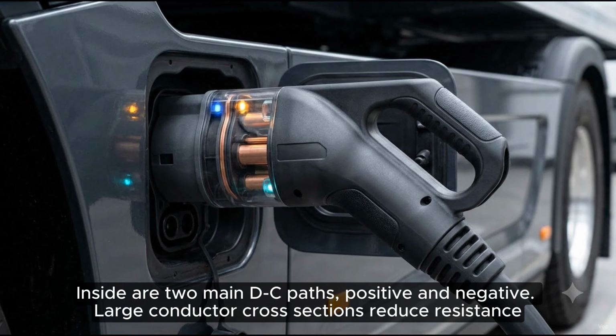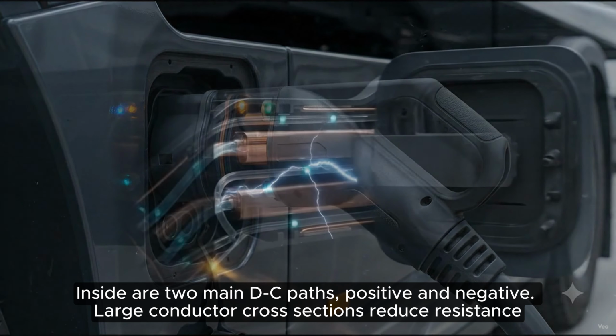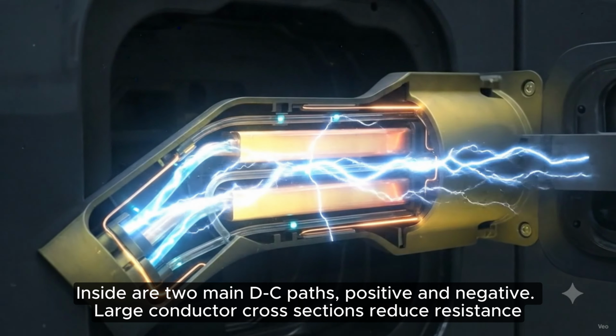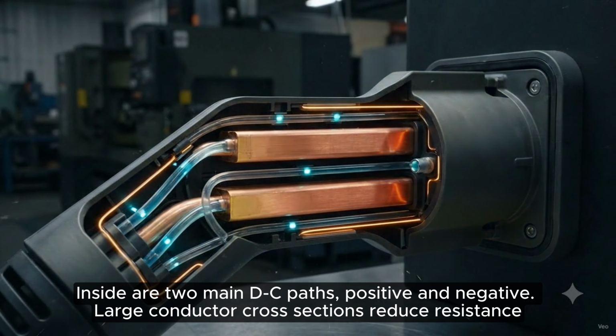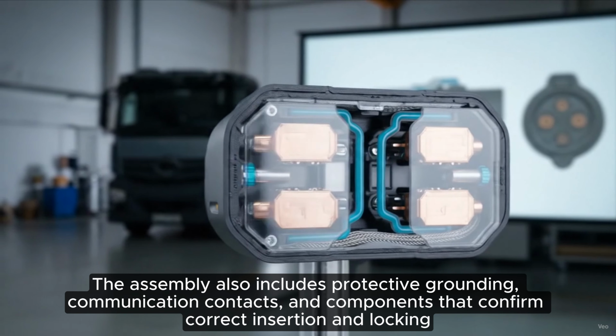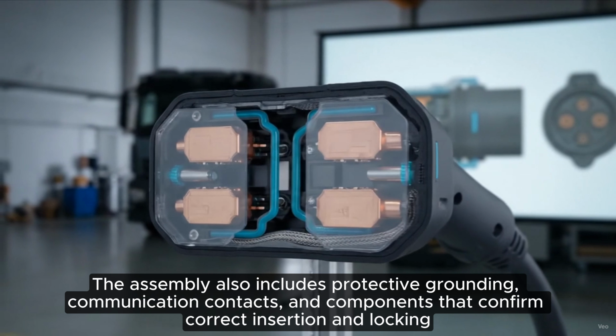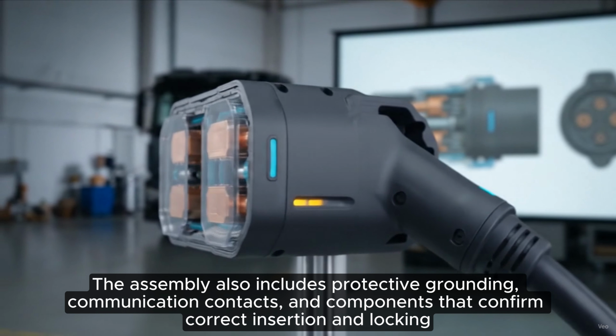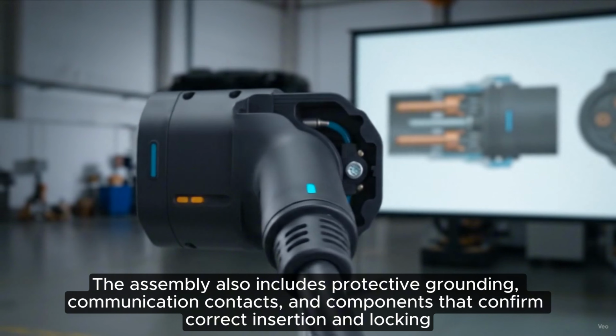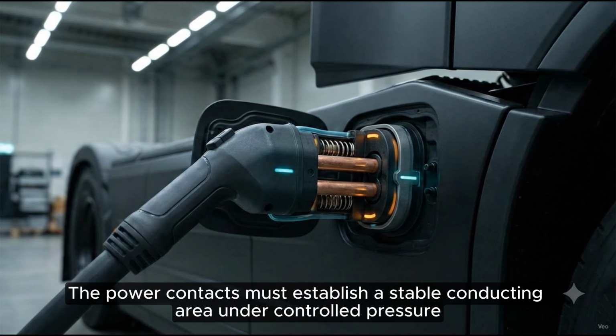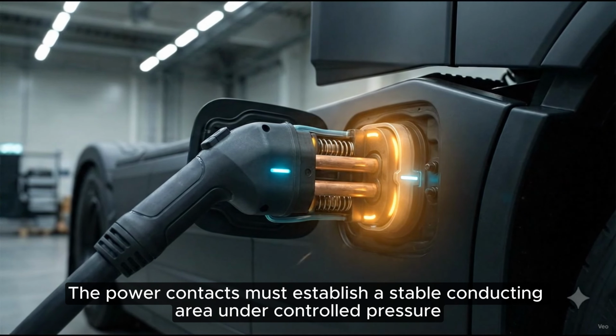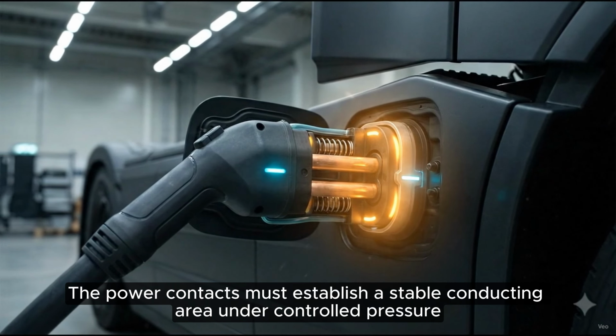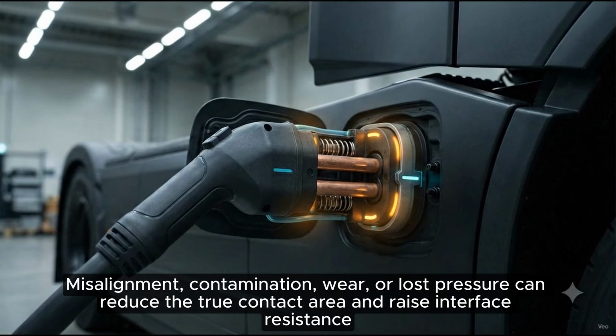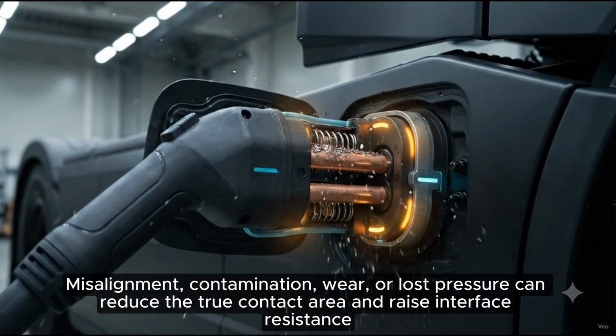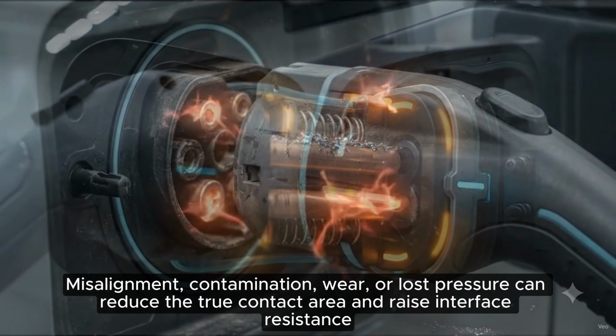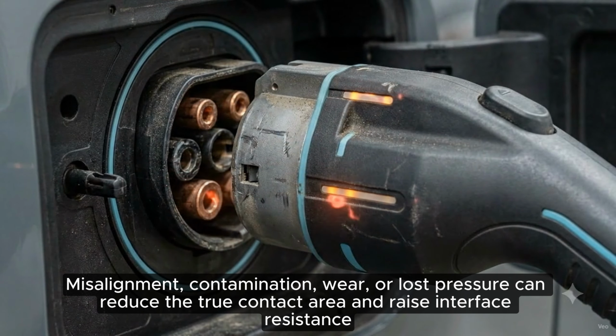Inside are two main DC paths, positive and negative. Large conductor cross-sections reduce resistance. The assembly also includes protective grounding, communication contacts, and components that confirm correct insertion and locking. Keying. The power contacts must establish a stable conducting area under controlled pressure. Misalignment, contamination, wear, or lost pressure can reduce the true contact area and raise interface resistance.